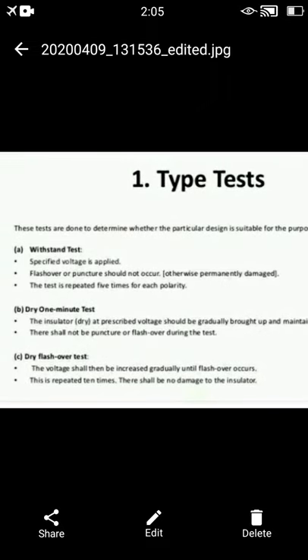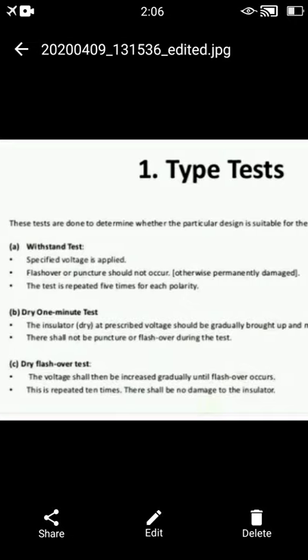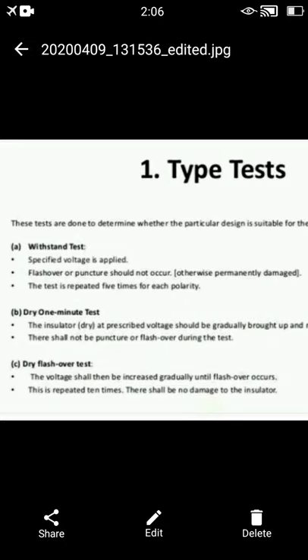The second type is the dry one minute test. For insulators that are dry, a prescribed voltage is gradually applied. There should not be a puncture or flashover during the test. The third type is the dry flashover test, in which the voltage is increased gradually until flashover occurs. This is repeated ten times and there shall be no damage to the insulator.